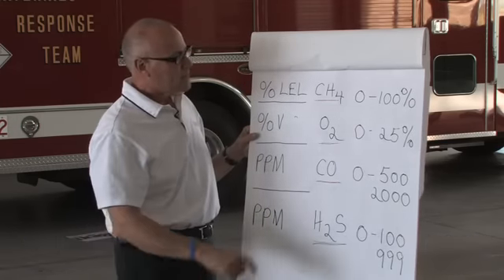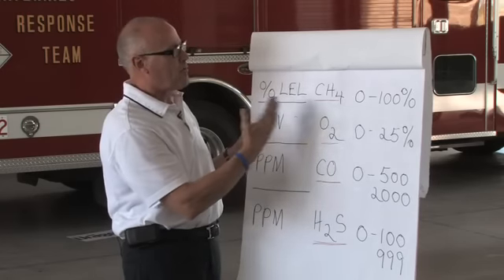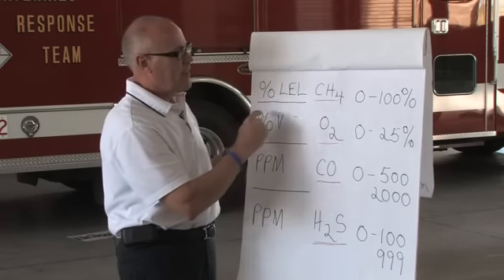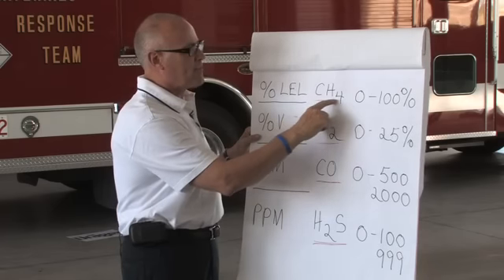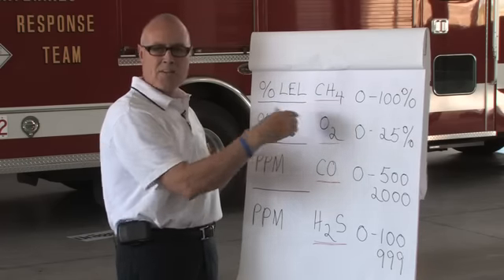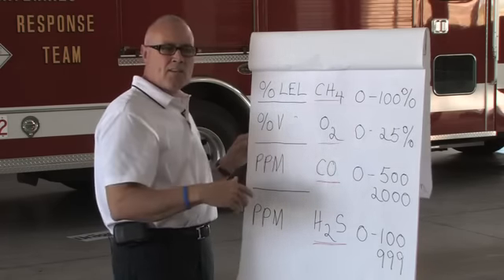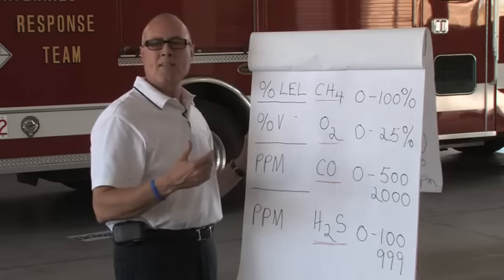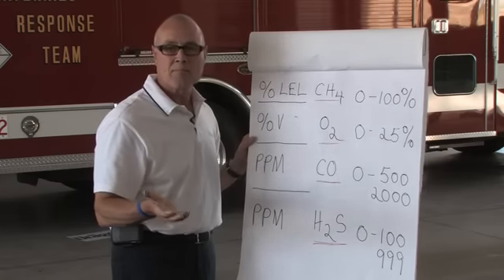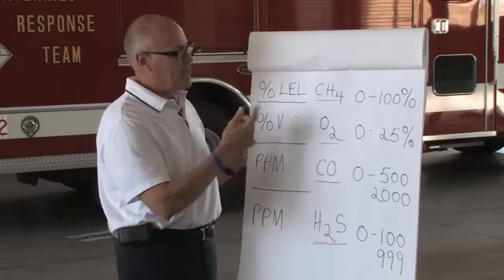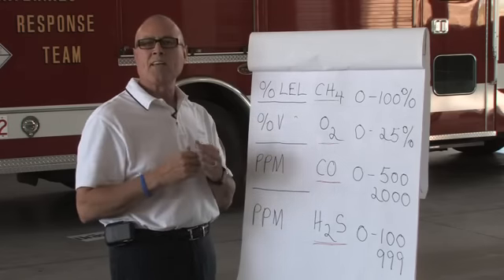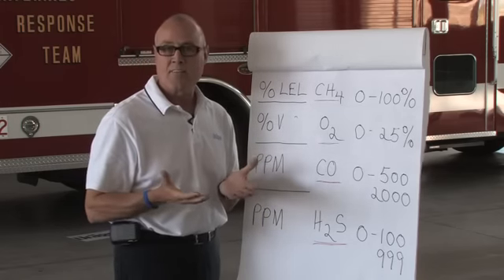And the reason that the alarms are so far down scale is because even though we're calibrating the instrument to CH4 or natural gas or methane, you could be out on a freeway monitoring gasoline vapors, and if the instrument's telling you, yeah, I've got 10% of the LEL, you might have 20% of the LEL.